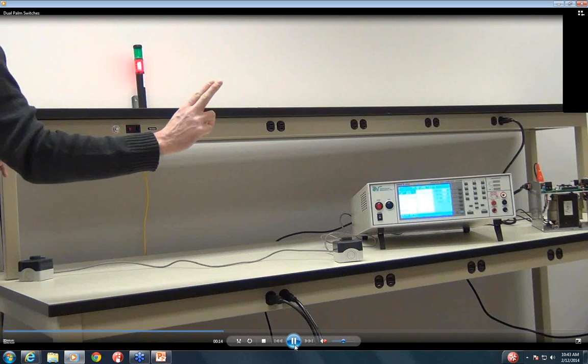So I tried to push the test button, but I have my PLC remote activated, so my HiPot test didn't run. I know the screen is a little hard to see, but on the HiPot tester, on the bottom right-hand side where the white, red, and black lead connections are, there's a little HV symbol — when the test starts, it flashes, indicating high voltage is outputting. So basically I tried to cheat and push the test button, but with the PLC remote activated, it won't let me do that. I have to use those switches.